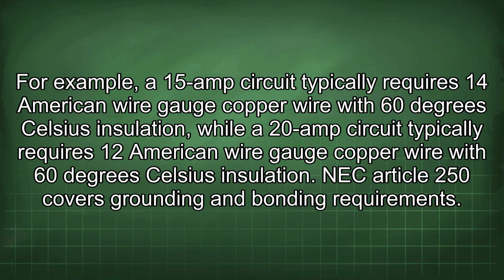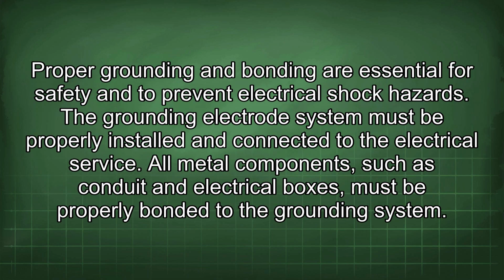NEC Article 250 covers grounding and bonding requirements. Proper grounding and bonding are essential for safety and to prevent electrical shock hazards. The grounding electrode system must be properly installed and connected to the electrical service. All metal components, such as conduit and electrical boxes, must be properly bonded to the grounding system.